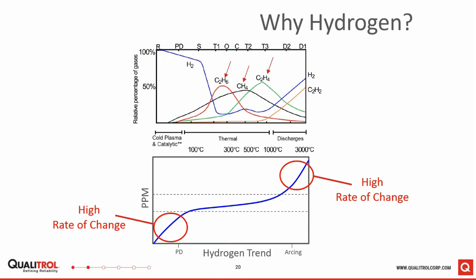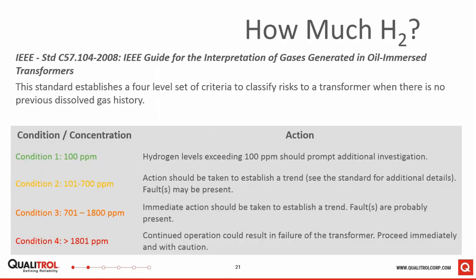Thanks, Matt. Okay, great insight there. So we've looked at why hydrogen. Let's just very quickly look at a few other questions. So how much hydrogen? This is quantified by the standard shown here. C57.104 details 4 separate conditions that can be designated by the concentration of hydrogen. Together with defining the concentration limits or ranges for hydrogen, IEEE also provides some guidance on actions to take if you reach or exceed those limits.